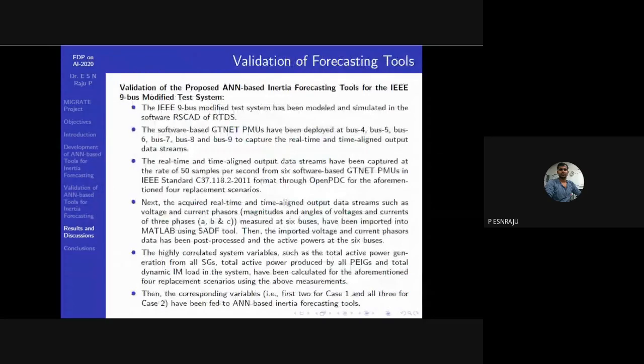This is the validation procedure I mentioned, reiterating for the IEEE 9-bus network. We modeled the same IEEE 9-bus system in the RTDS RSCAD and simulated it. As mentioned, we have the software GTNet PMU, and we can also use hardware-based PMUs connected to the RTDS platform to capture phasor data from all buses—voltage phasors, current phasors, voltage angles and magnitudes—from which we measure active and reactive powers. We capture all the power system variables using these GTNet PMUs.